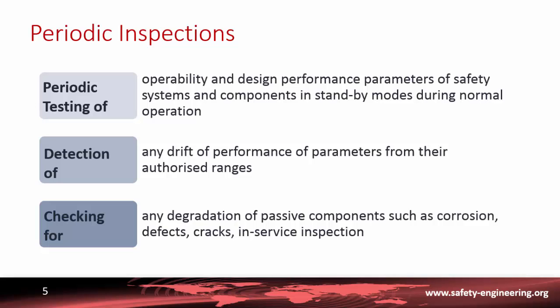The second element of the operating rules is periodic inspection and testing. These are used to test the operability and design performance parameters of safety systems and components which are in standby mode during normal operation. These tests are performed depending on the system every two weeks, every month, or at every outage each year.